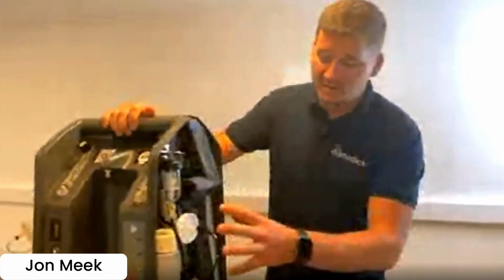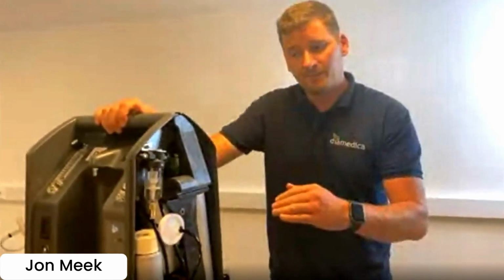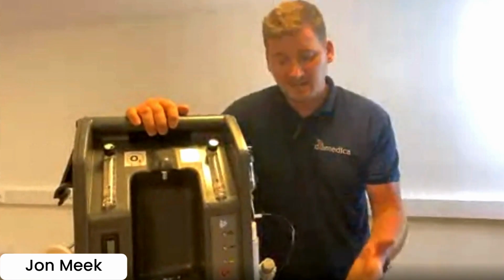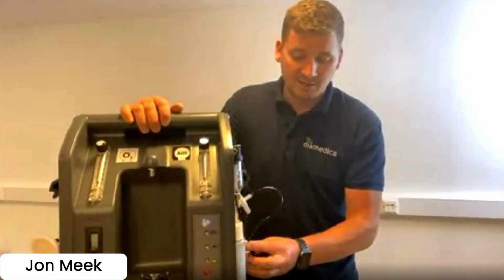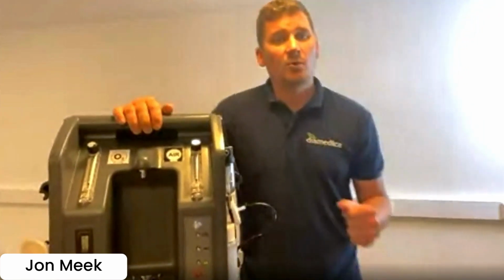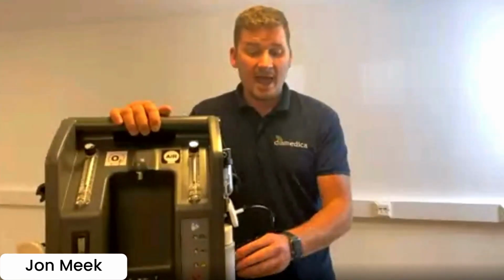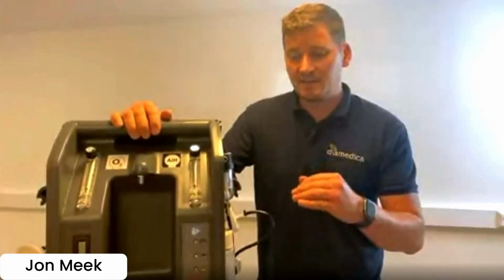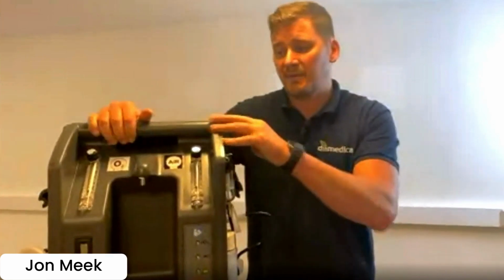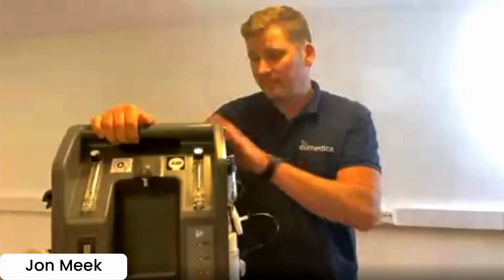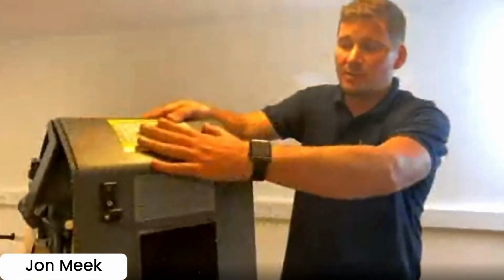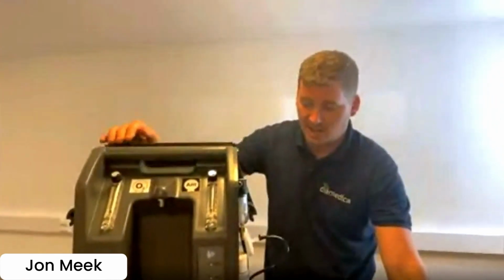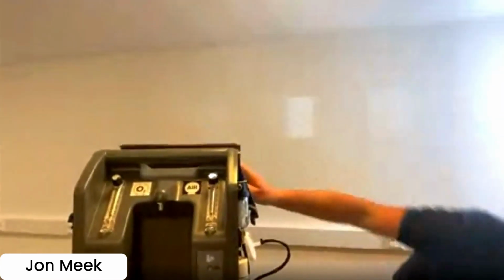We used to have an accumulator tank fitted in here to control the flow, to make sure the airflow meter was steady, so you had a steady output. And now we've gone to a different regulator, which now eliminates the need for an oxygen air tank to steady the flow. So everything has been designed to ensure a safe CPAP flow is delivered. I won't go too much into this because we'll show you going forward. On the back, we have a simple mixing chart, but I'll show you on the slide in a minute as we go forward. So this was the AirSet one. So this is the one we first had our derived CPAP.